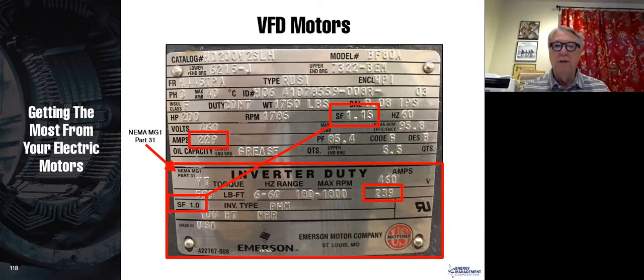Most motor nameplates don't have that, and you actually have to go to the data sheet or maybe even call the manufacturer to find that out. But when we talk about what is an inverter duty rated motor, that is the first thing you want to look at, and we'll talk about that momentarily. Now, next is service factor. Notice that when we're running this thing across the line, this is a 1.15 service factor motor, and when we're running it on an inverter, it's only a 1.0 service factor motor.